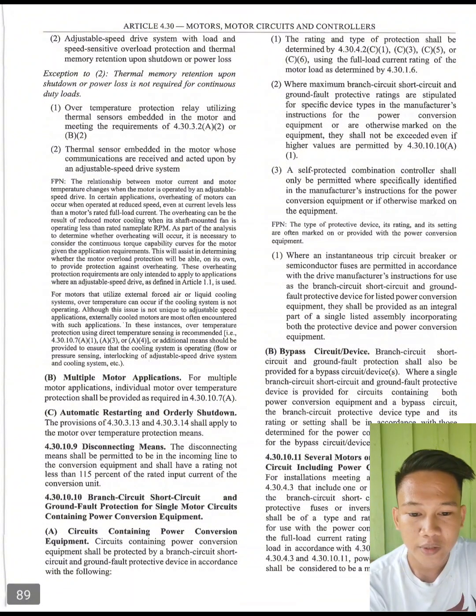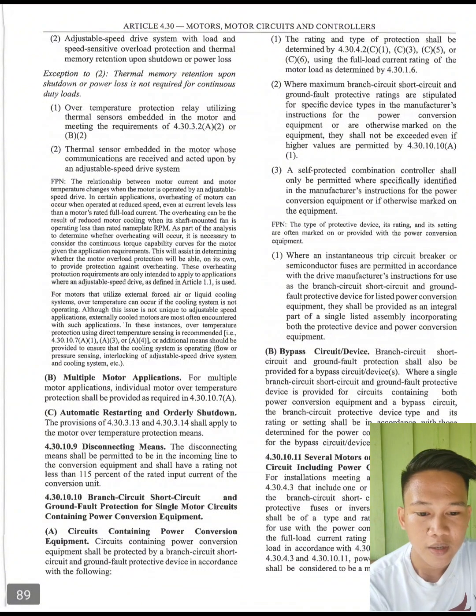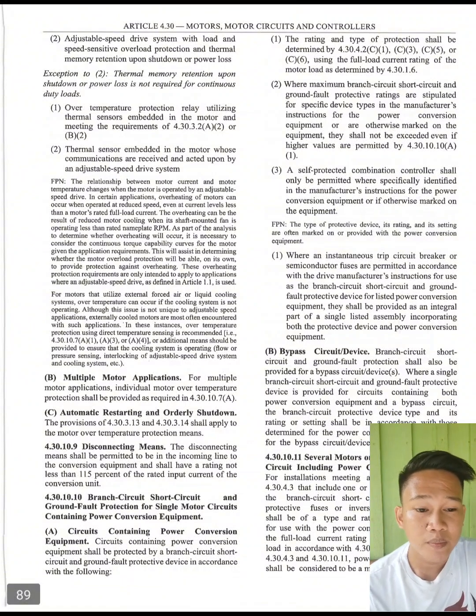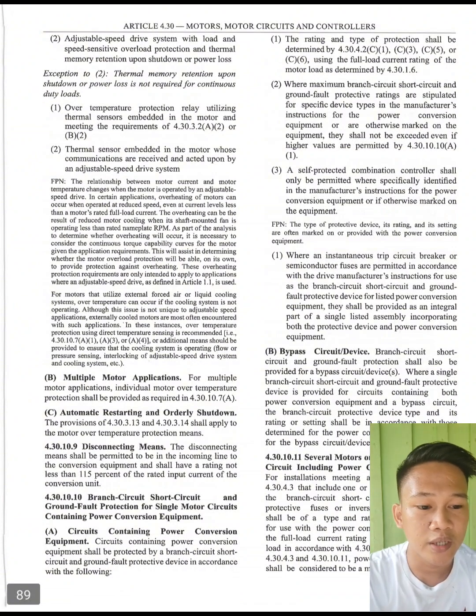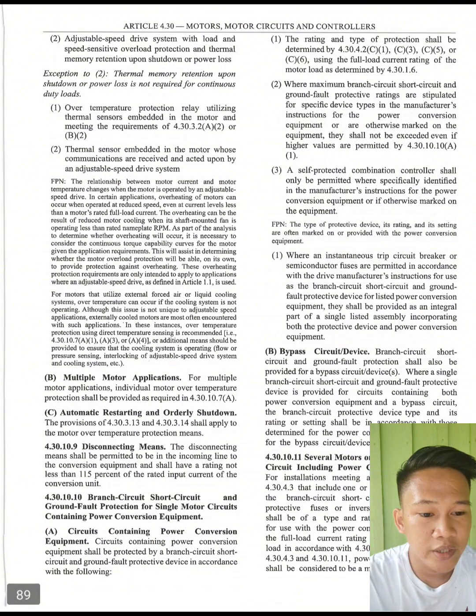Next, we have 4.30.10.10 branch circuit, short circuit, and ground fault protection for single motor circuits containing power conversion equipment. So, first, we have circuits containing power conversion equipment. Circuits containing power conversion equipment shall be protected by a branch circuit, short circuit, and ground fault protective device in accordance with the following. First, the rating and type of protection shall be determined by 4.30.4.2, C1, C3, C5, or C6 using the full load current rating of the motor load as determined by 4.30.1.6. Where maximum branch circuit, short circuit, and ground fault protective ratings are stipulated for specific device types in the manufacturer's instructions for the power conversion equipment or are otherwise marked on the equipment, they shall not be exceeded even if the higher values are permitted by 4.30.10.10a1.